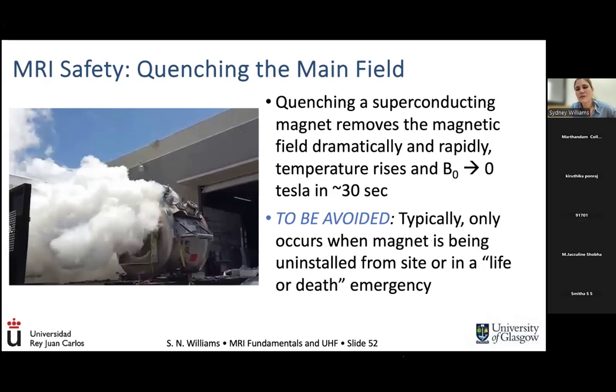And so you really don't want to lose that scanner and the main magnetic field if possible. But in the case of a life or death situation, if someone was stuck to the scanner themselves because of a ferromagnetic projectile material, then there is an option called quenching the magnet, or quenching the magnetic field. So in every MRI facility, there will be a button somewhere inside on the wall, big, with a lot of signage, for the emergency quench button.